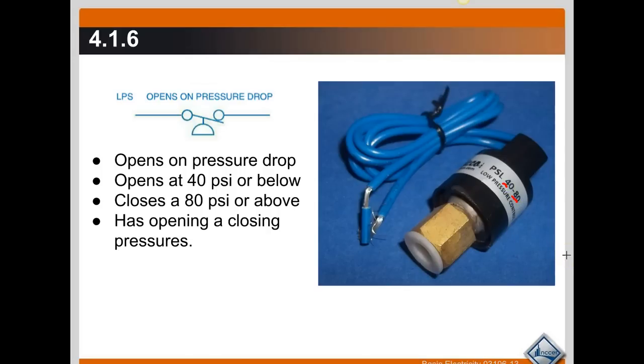So again, on this one, the cut-out pressure, where it's going to open the switch or cut the circuit out, is 40 psi G. And the cut-in pressure, or where that switch reconnects, is at 80 psi G.